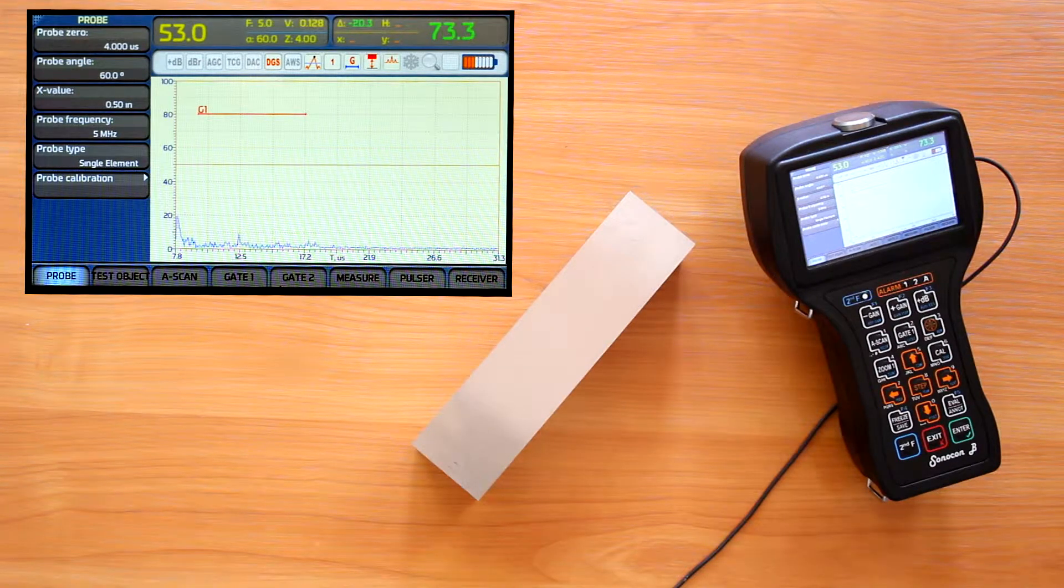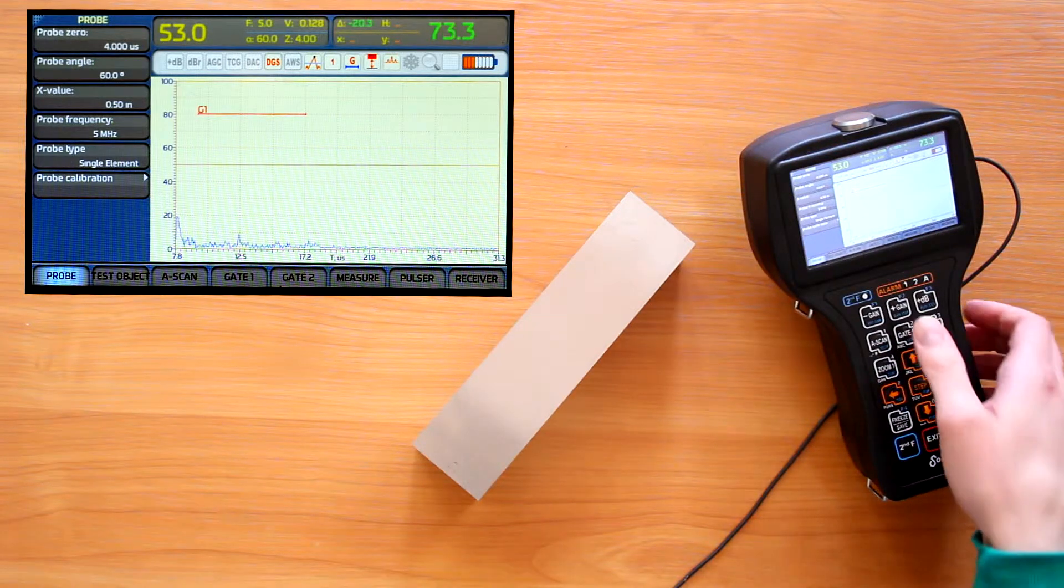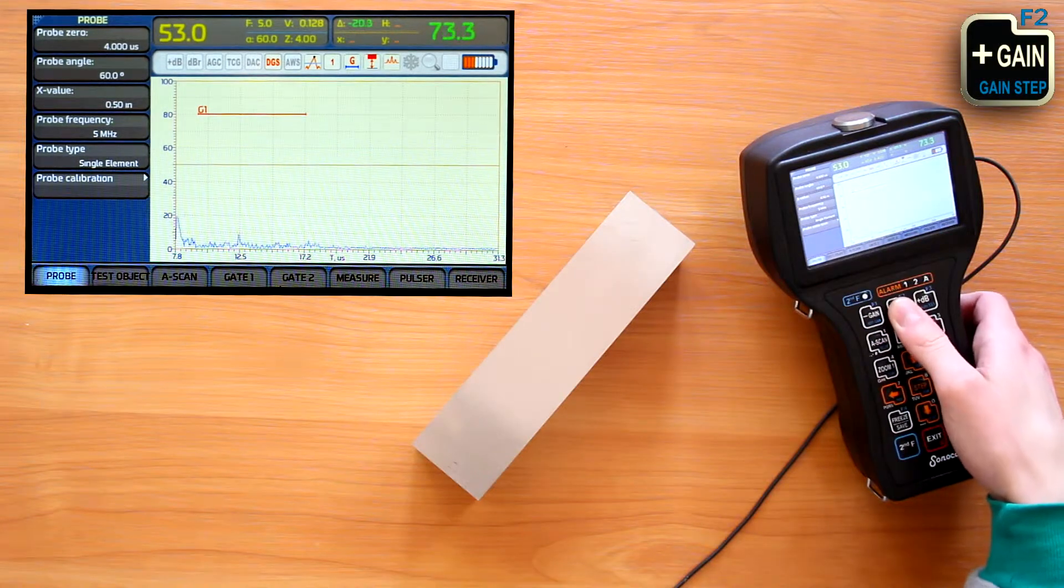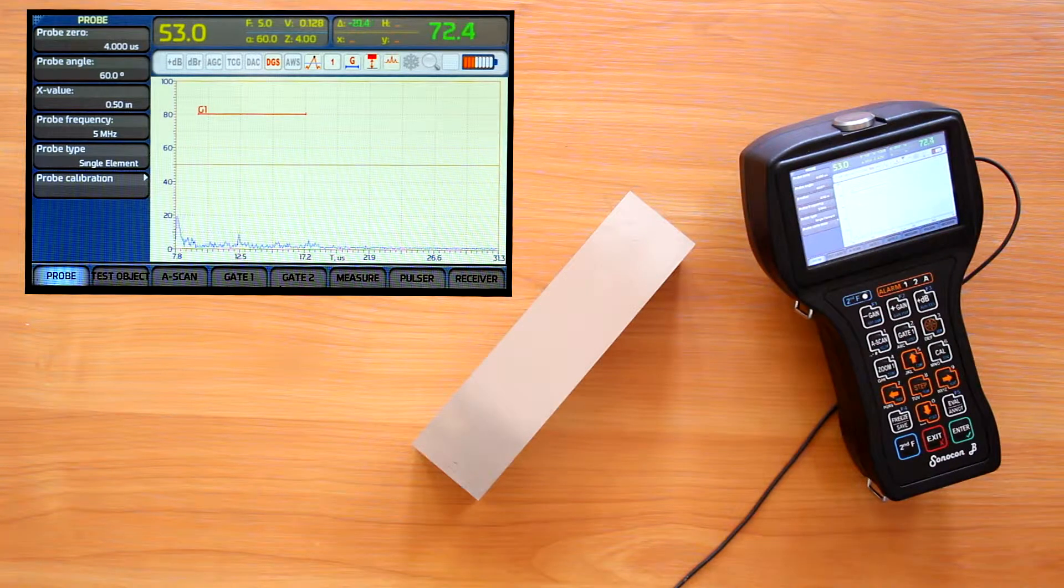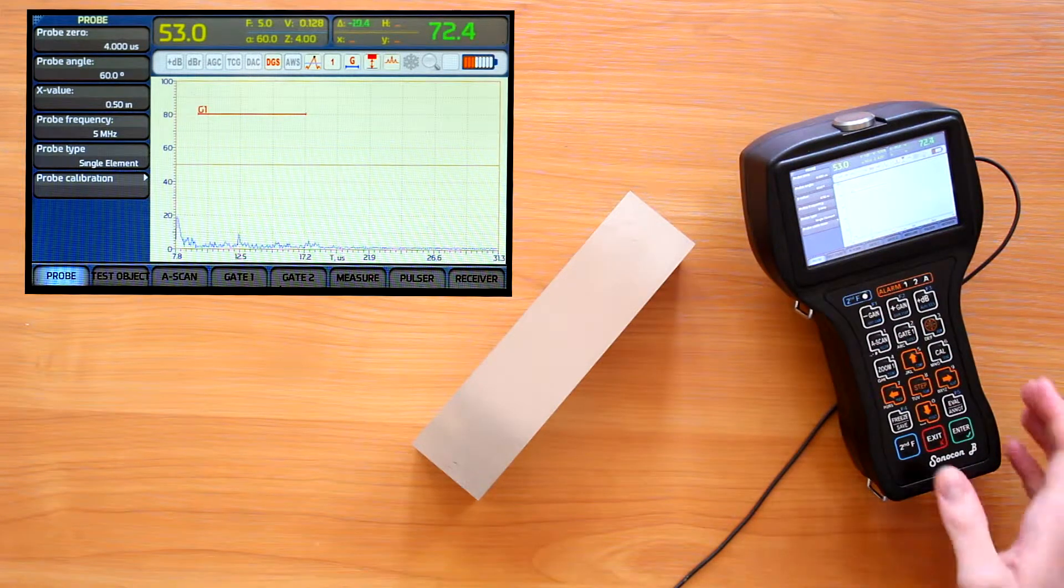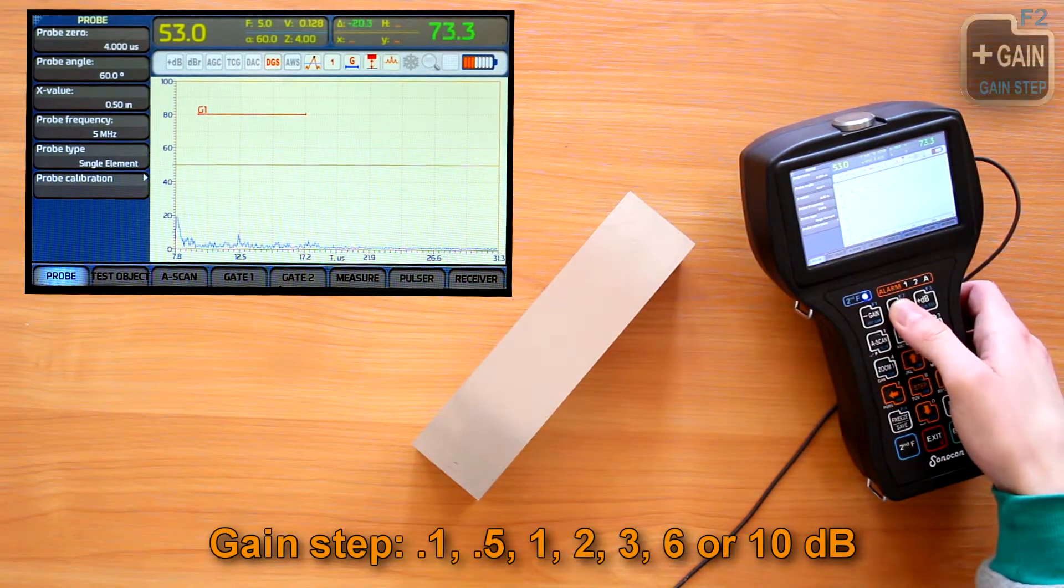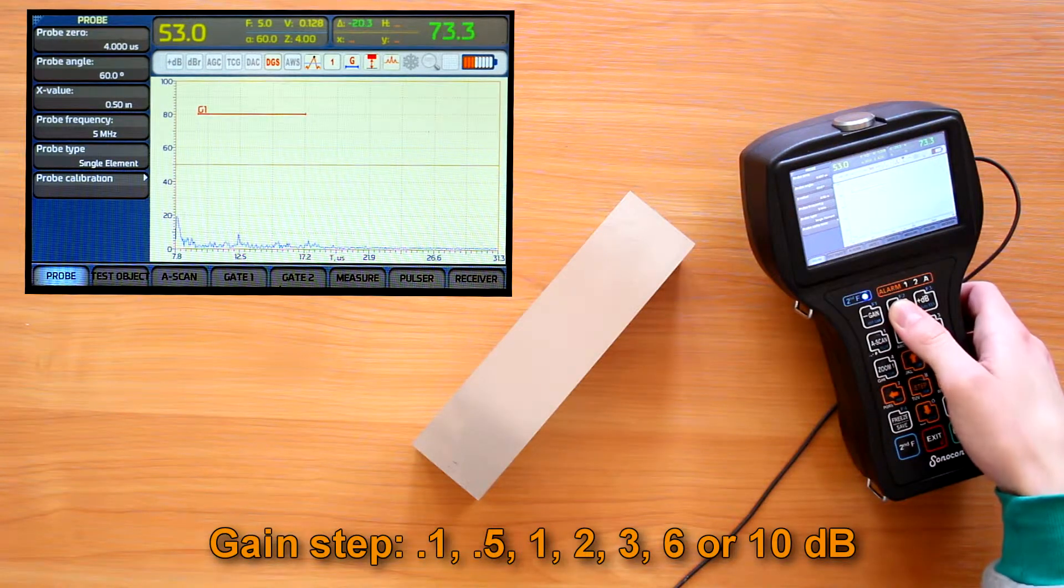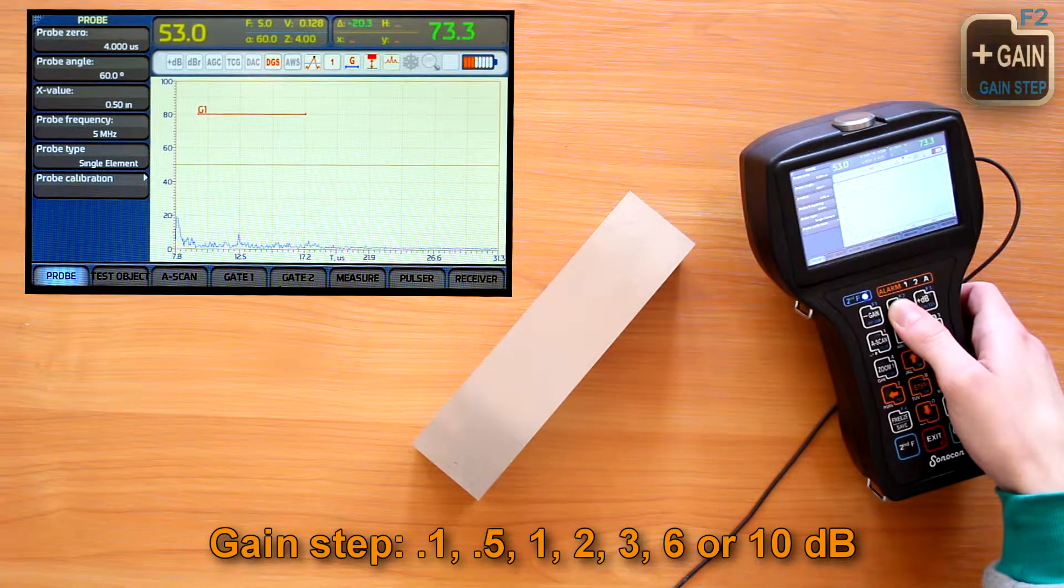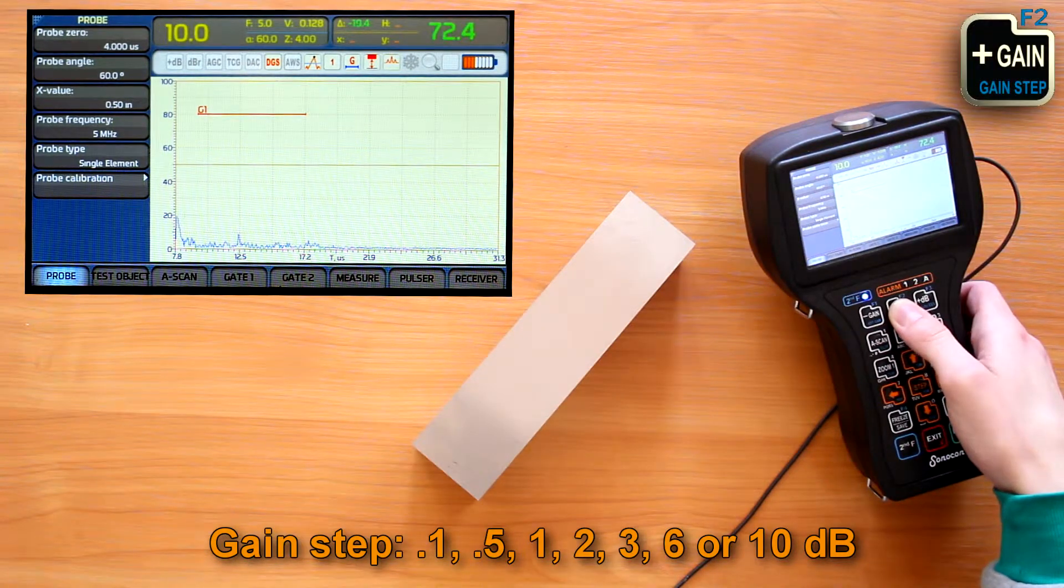First of all, we can adjust the gain value with gain minus and gain plus buttons. We also can choose the step of this adjustment with second function plus gain plus. From this set: 0.1, 0.5, 1, 2, 3, 6 or 10 decibels.